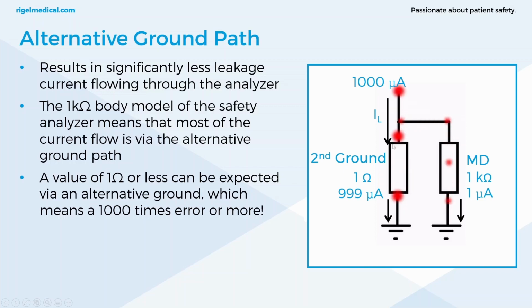Now, if you look at the example in the image, compared to the 1 kilo ohm resistance of the body model, the secondary ground path here is just an arbitrary value of 1 ohm, which is a typical value you're going to measure. Values of 1 ohm or less can be expected via an alternative earth. So that means you could be getting a 1,000 times error or more. Again, our safety analyzers do have a warning if a secondary earth path is detected.